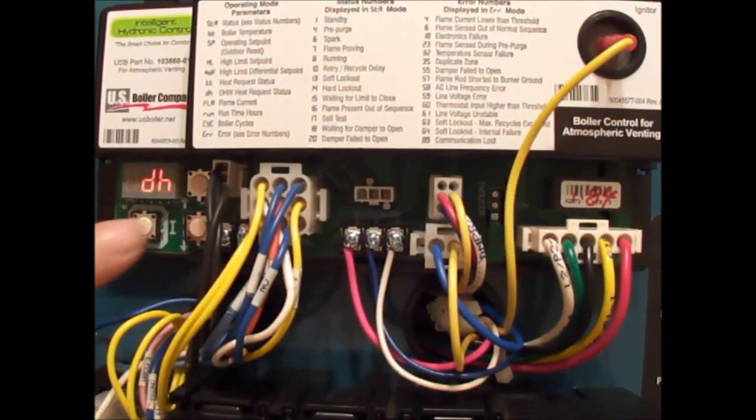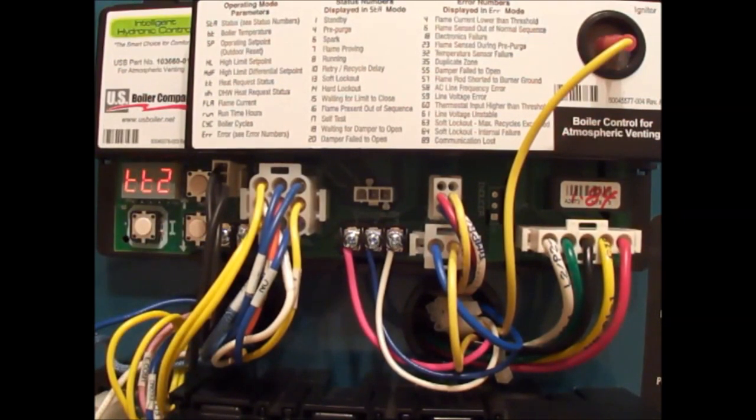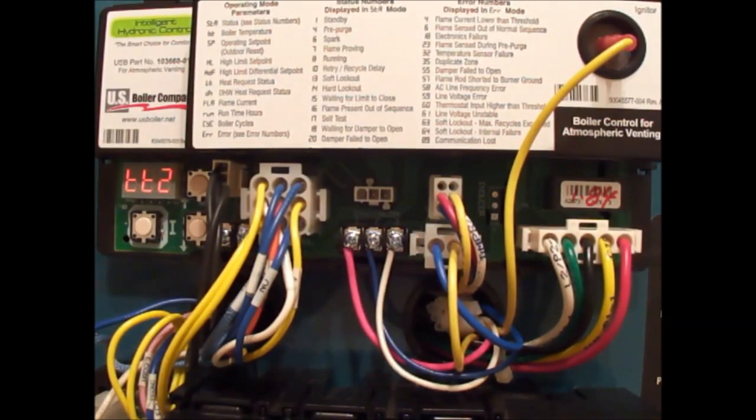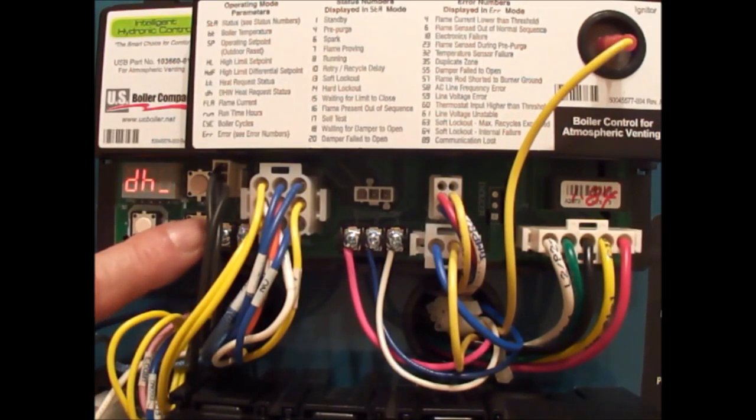Domestic hot water, we can change that to domestic hot water or TT2. TT2 is your second zone of heat. This control can do two inputs. It can be two heat zones, one heat zone one domestic hot water. We can change domestic hot water to TT2 and that makes it a heat zone again that ignores priority. If we leave it in DH, then it would not ignore priority and it would shut down the heating pump.